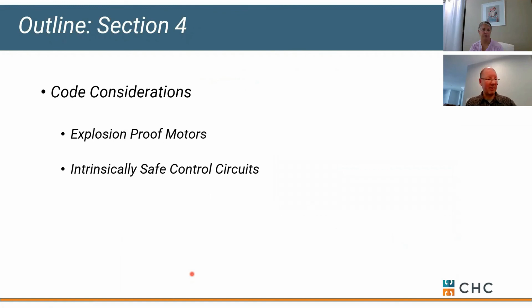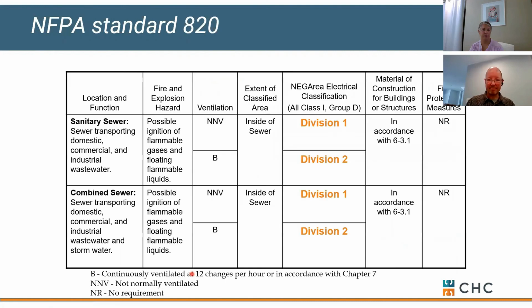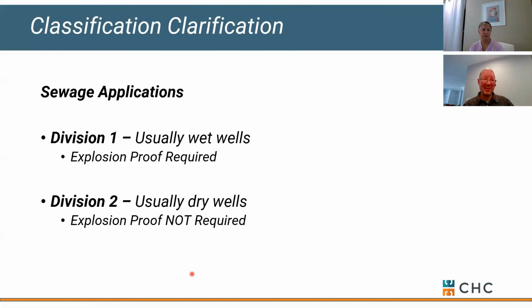Okay, my last little section here. We're getting close on time, and that's understanding explosion proof and understanding intrinsically safe controls. The National Fire Protection Agency, NFPA, has standards for Division 1 and Division 2 requirements. Now, I'm terrible at these, so my next slide is a quick little summary. I hate codes in general, but anything that's got sewage in it tends to have the potential for methane gas. So if you've got a basin that's got sewage involved, most inspectors are going to require an explosion-proof motor, or highly recommend it.